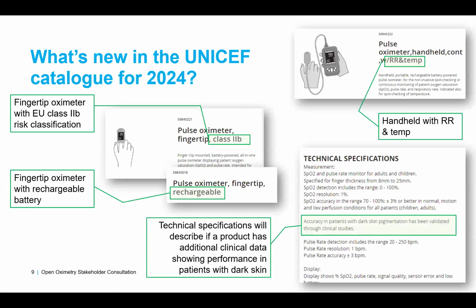So just to point out a couple of things that are new for us. As I mentioned, this fingertip issue, we ended up qualifying products that had a 2A risk classification, but we also accepted the one that had 2B. But we created a separate material number, a product number, for this one, to set it apart from the others, because as you can imagine, there was a big cost difference. We didn't want to lump all of our fingertips together when there was this key difference.